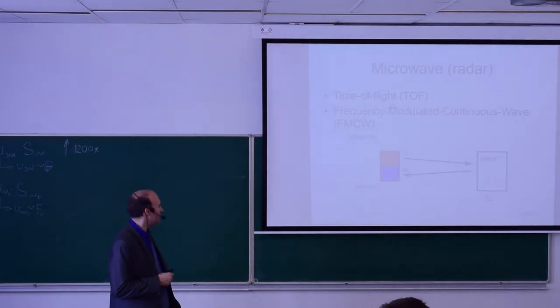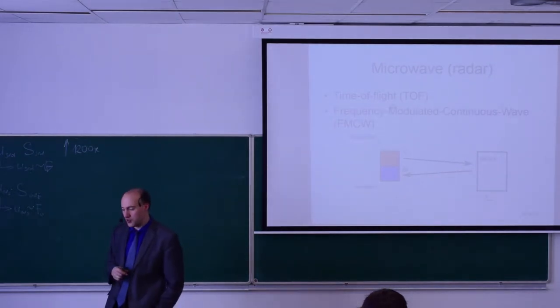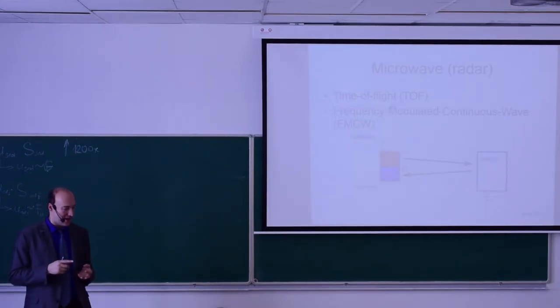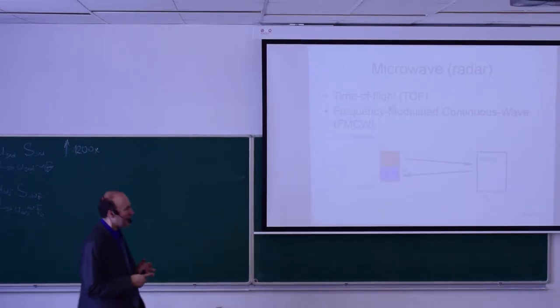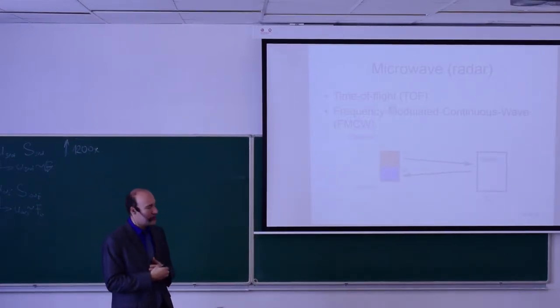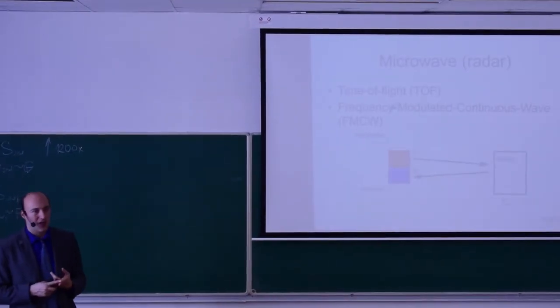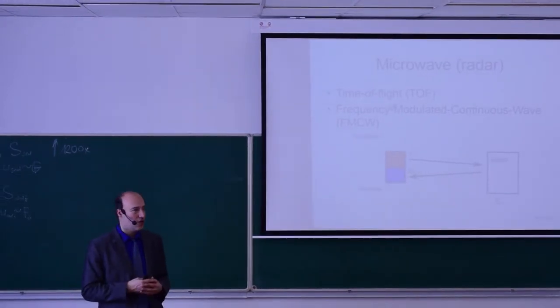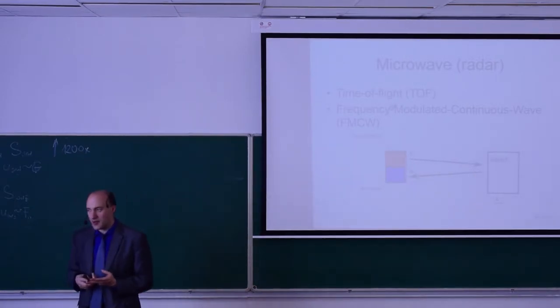For the moment we'll stick with continuous sensors, and this is the microwave or radar position sensor. It is a sensor for position, a sensor for speed, and it can be used quite often as a liquid level sensor as well. A microwave sensor is based on the measurement of reflections from an object — you have a transmitter, a receiver, and you are looking for the echo you receive from some liquid level or from some object.